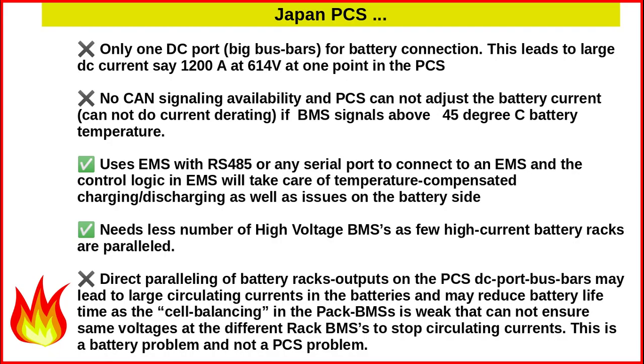I myself have tested a Japan PCS where it was drawing 1000 ampere discharge current from batteries at 614 volt. So such a large current at one point is one issue. If you compare this PCS with China PCS, the China PCS will have more than 2 DC battery ports, and therefore the currents are distributed at different DC ports or battery ports in case of China PCS. But in the Japan PCS, we have this particular feature of large currents concentrated on a single DC port meant for the batteries.